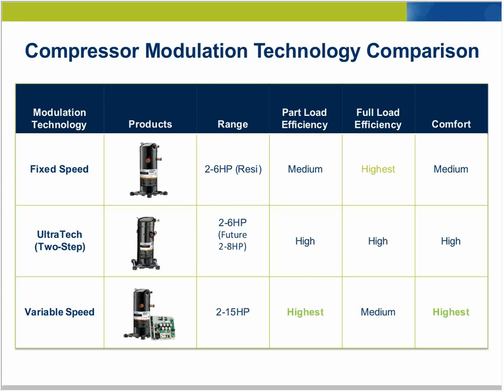But if you're really looking for more energy efficiency and a higher level of comfort, you need to look at the next two rows. Those are modulating technology. By that, it modulates on the compression side as well as on the airflow side. So two stage is in 2 to 6 horsepower today, has very good part load efficiency, and it also has very high full load efficiency. So that's a technology that does well across the board, and it has a high level of comfort as well.